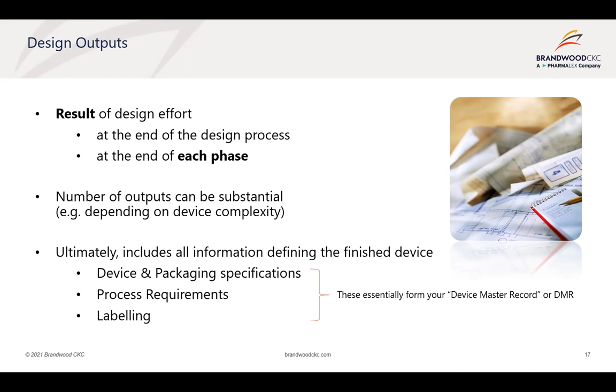Ultimately, the outputs include the information that defines the finished device, such as the device specifications, packaging specifications, the process requirements for you to manufacture and utilize the product in the field, and the labeling information that accompanies the device. All of the outputs generated as part of that process form your device master record, which we'll touch on a bit later.